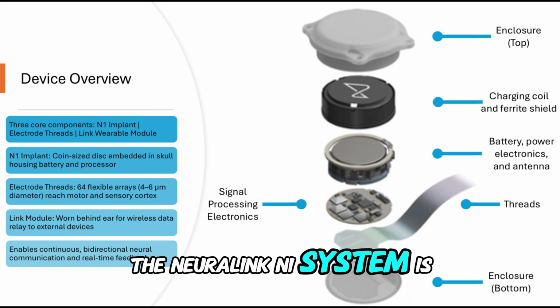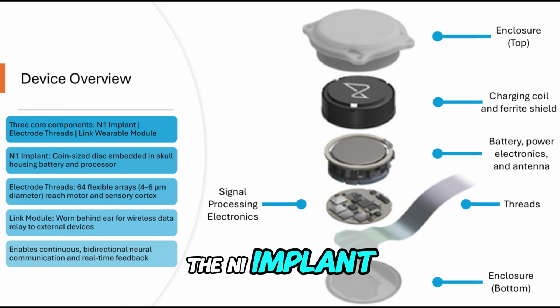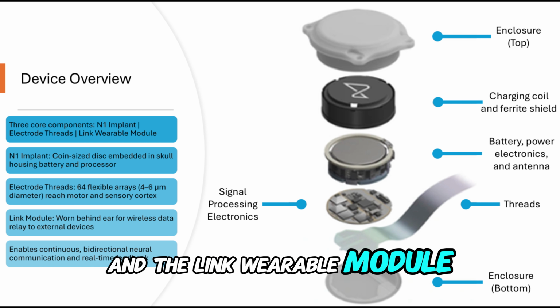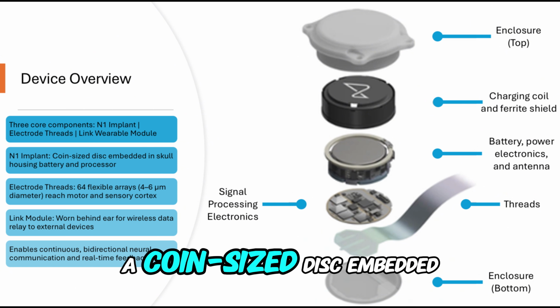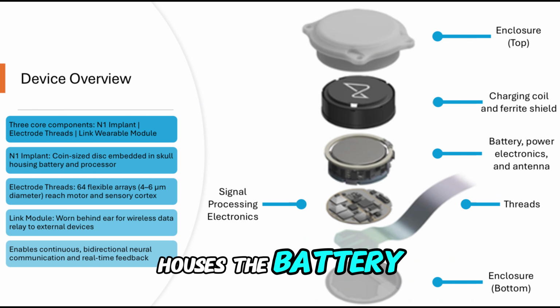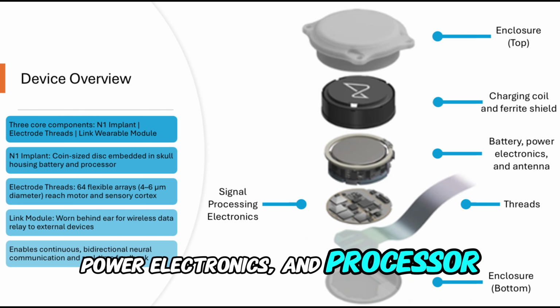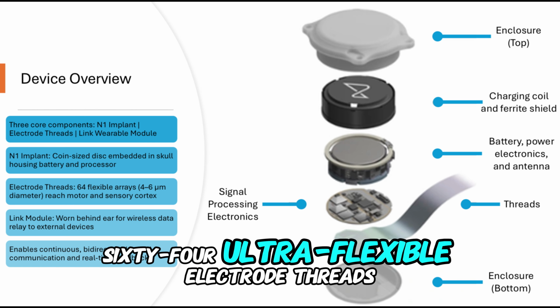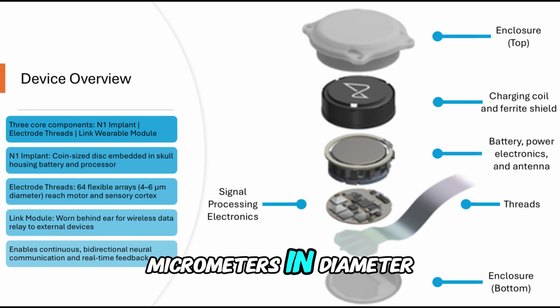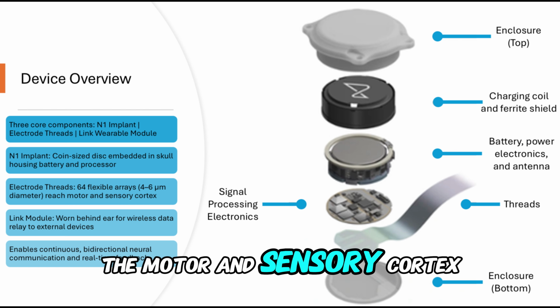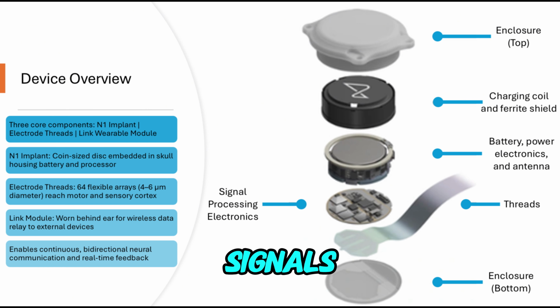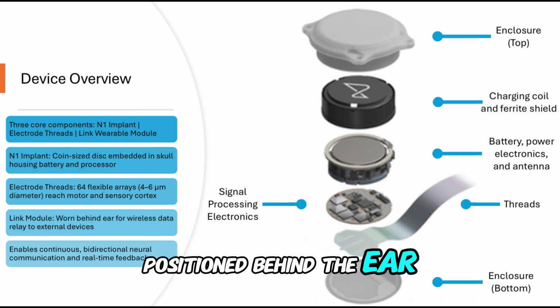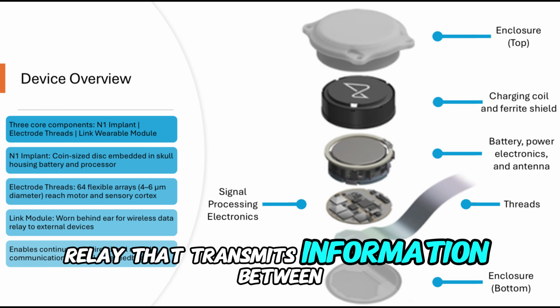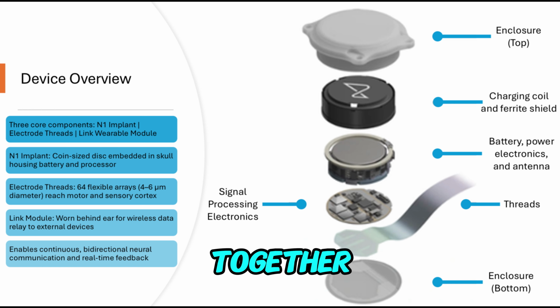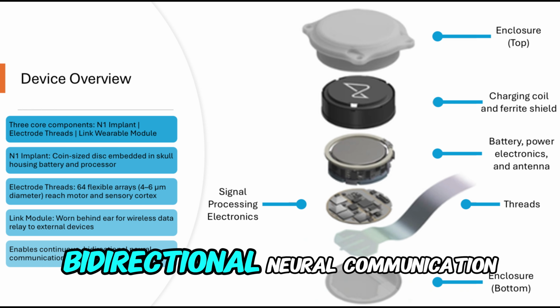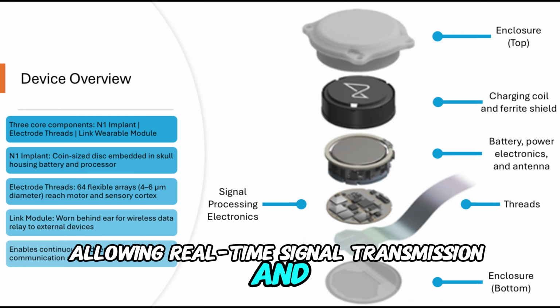The Neuralink N1 system is made up of 3 main components: the N1 implant, the electrode threads, and the Link wearable module. The N1 implant itself is a coin-sized disc embedded directly into the skull and houses the battery, power electronics, and processor. Extending from the implant are 64 ultra-flexible electrode threads, each about 4 to 6 micrometers in diameter, which connect to regions of the motor and sensory cortex to record and stimulate neural signals. The Link module, positioned behind the ear, serves as a wireless data relay that transmits information between the brain and external devices. Together, these components enable continuous bidirectional neural communication, allowing real-time signal transmission and feedback between the brain and digital systems.